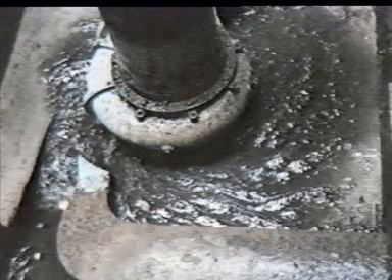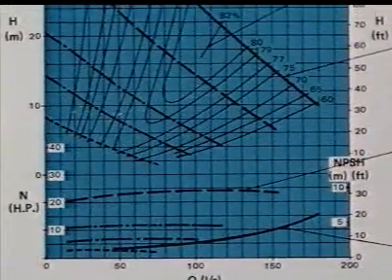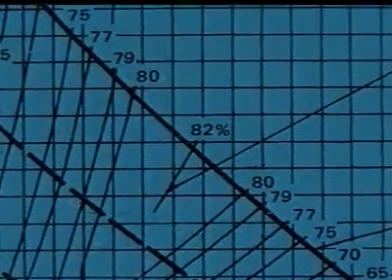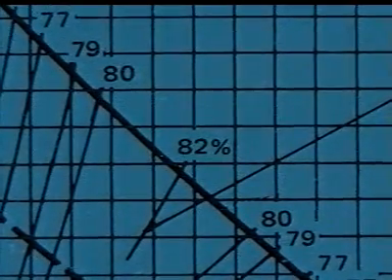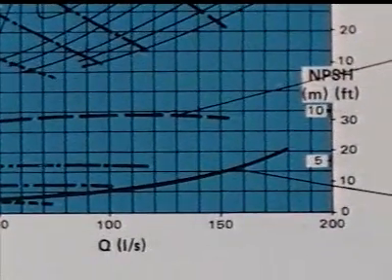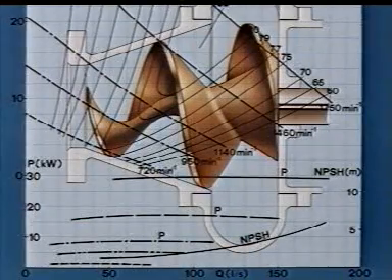Thus at maximum operation, the motor will not draw high current. The pump can operate at its full range of pump performance curve. High efficiency of up to 82%, saving energy of up to 50% compared to torque flow pumps. The pump's low NPSH requirement enables it to move sludge even when the suction head decreases. The Hidrostal screw impeller does have superb pump performance.